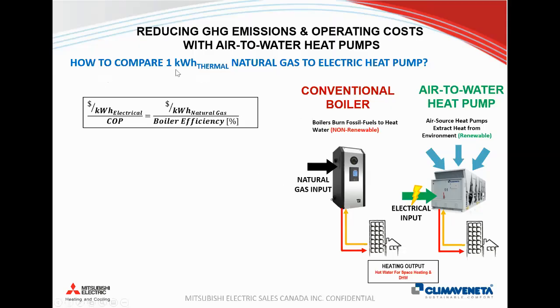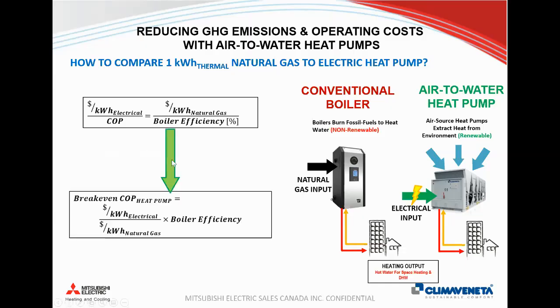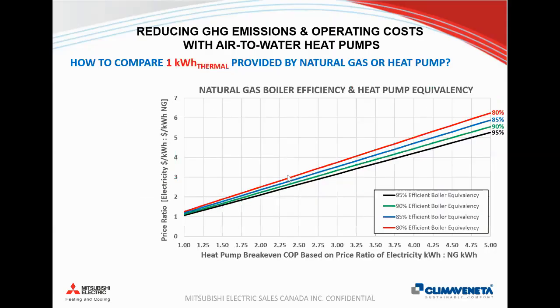So we can equate the two together and come up with this equation, and we can rearrange it to calculate a break-even COP for the heat pump. Rearranging this equation, you can express the break-even COP not with discrete costs of energy, but with the ratio of cost between electricity and natural gas. Dollars per kilowatt hour of electricity divided by dollars per kilowatt hour of natural gas, times the boiler efficiency, will tell us what COP the heat pump needs to operate at in order to be cost neutral, so the same cost to operate a heat pump or a boiler. Then we can plot that equation.